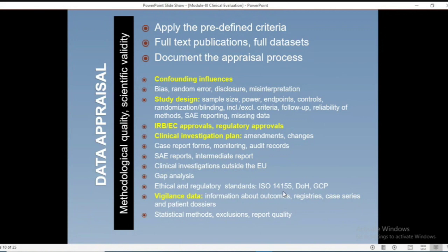This is the good clinical practice ISO required for clinical evaluation, ISO 14155. DOH, Department of Health regulation. GCP, good clinical practice. Vigilance data: just like in drugs we have pharmacovigilance, in medical devices it is called materiovigilance.